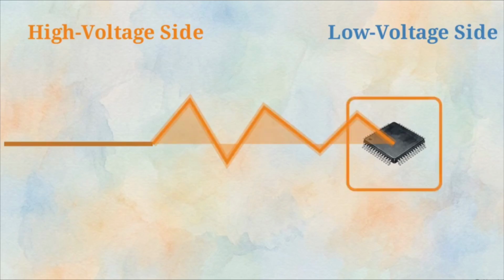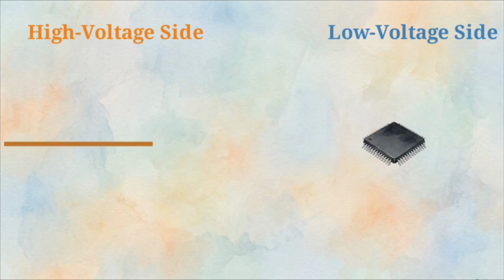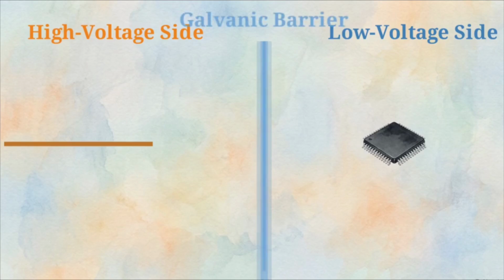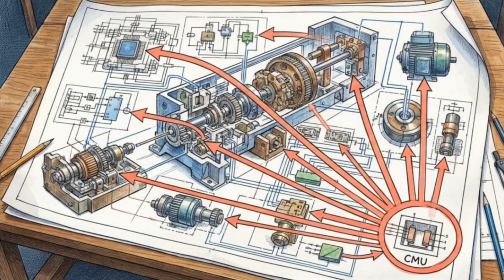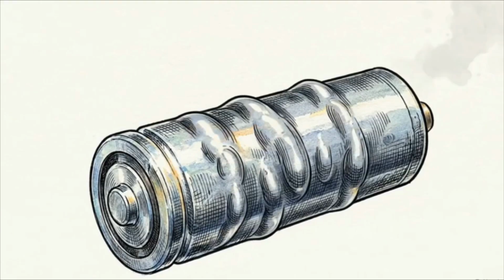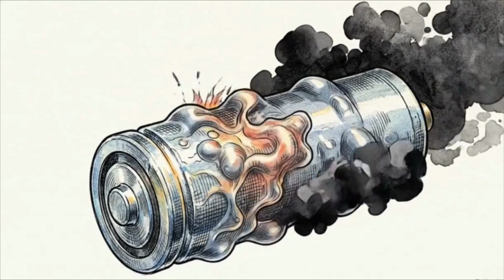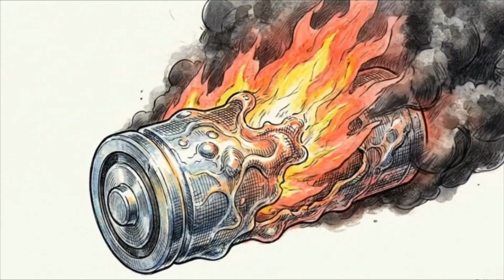A sudden voltage spike from the high voltage paths could destroy adjacent measurement hardware. To solve this, the CMU passes collected data through isolated communication channels. These galvanic barriers physically block high voltage current from crossing over. This isolated analog measurement is the primary input for every safety calculation that follows. If the data from the cells is inaccurate, the entire system's ability to prevent thermal runaway is compromised.